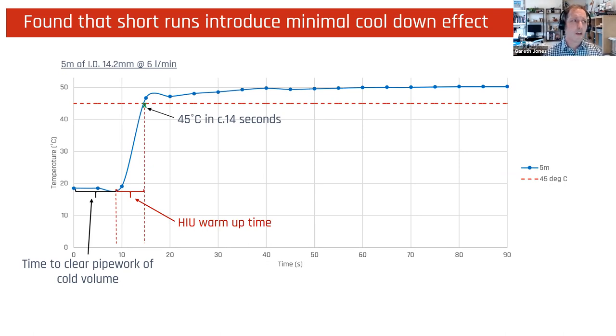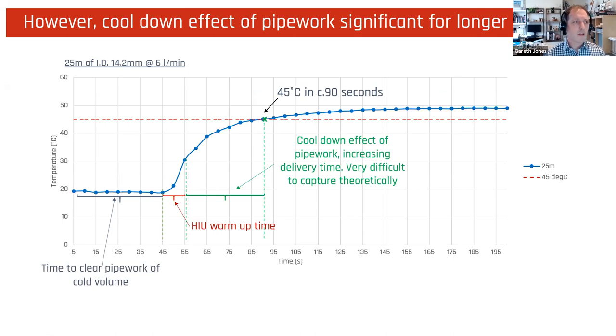What we found is that short runs introduce minimal cooldown effects. So this is an internal diameter of 14.2 millimeters at 6 liters per minute. And what you see is you get to 45 degrees in about 14 seconds. So this is only 5 meters. So you've got, at the bottom, the time to clear the pipe of cold volume, about 8 seconds. Then you've got your HIU warm-up time, about 6 seconds.